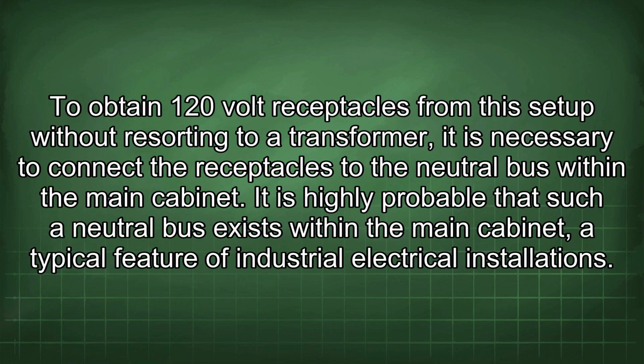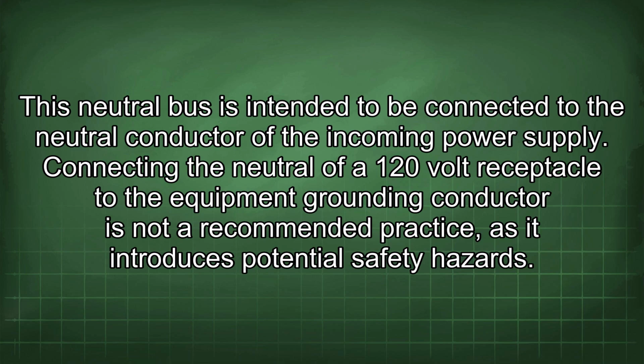To obtain 120 volt receptacles from this setup without resorting to a transformer, it is necessary to connect the receptacles to the neutral bus within the main cabinet. It is highly probable that such a neutral bus exists within the main cabinet, a typical feature of industrial electrical installations. This neutral bus is intended to be connected to the neutral conductor of the incoming power supply.